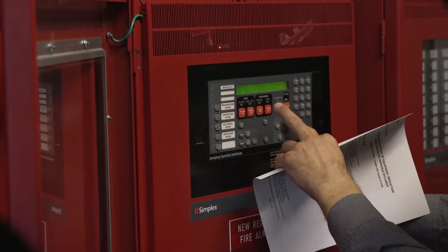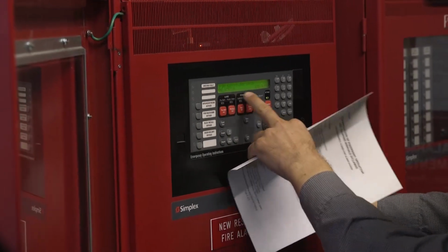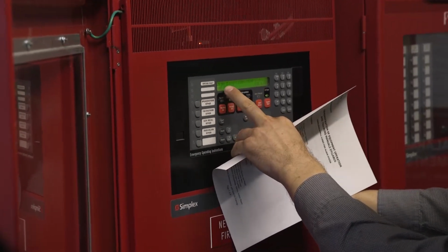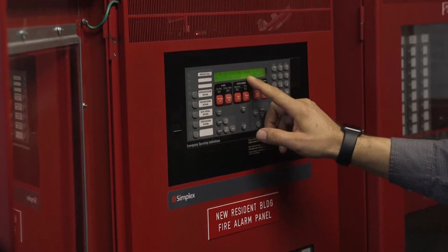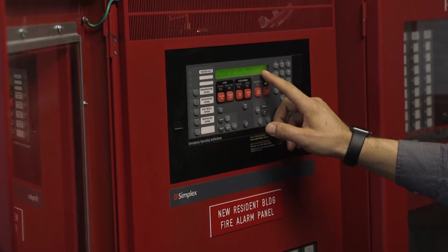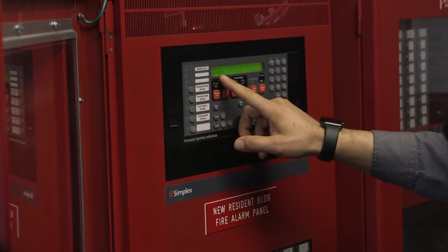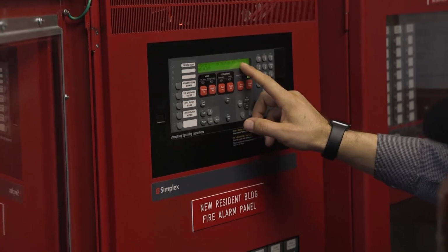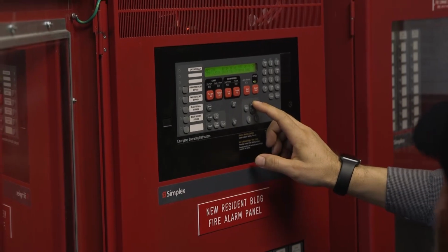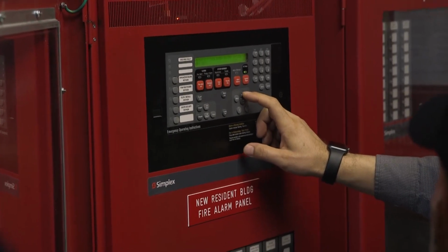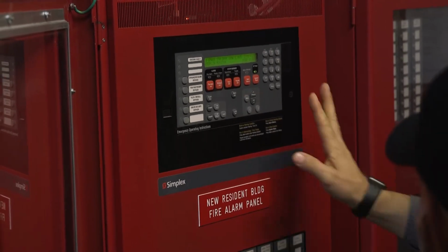It's a lot of resets. Every reset records, and you see smoke detector, floor 5, service elevator, lobby, corridor 300. 15-82 smoke detector was activated on July 24 at 11:19, and so on. You go back, you see more alarms. All this is stored inside this panel.